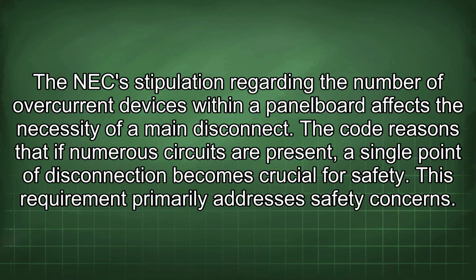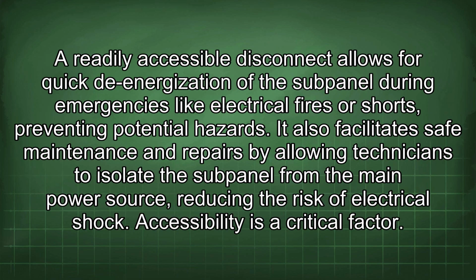The NEC stipulation regarding the number of overcurrent devices within a panel board affects the necessity of a main disconnect. The code reasons that if numerous circuits are present, a single point of disconnection becomes crucial for safety. This requirement primarily addresses safety concerns. A readily accessible disconnect allows for quick de-energization of the subpanel during emergencies like electrical fires or shorts, preventing potential hazards. It also facilitates safe maintenance and repairs by allowing technicians to isolate the subpanel from the main power source, reducing the risk of electrical shock.